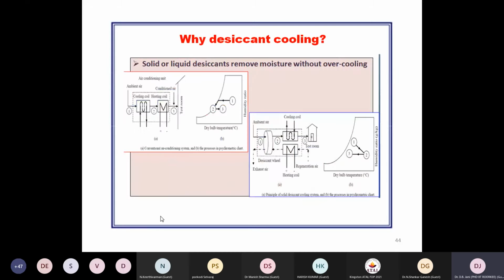So this is a very important diagram that can explain to us the working of conventional cooling as well as the working of desiccant cooling. First of all, we have to go through conventional cooling. Ambient air, if it is an open system, can be taken in, and it gets cooled in the cooling coil. Sometimes, with the aim of dehumidification, we may drop its dew point temperature by maintaining the surface coil evaporator temperature at a very low value. So the supply air reaches overcooling. So again, you may provide reheating and supply it at typical design conditions to the test room.